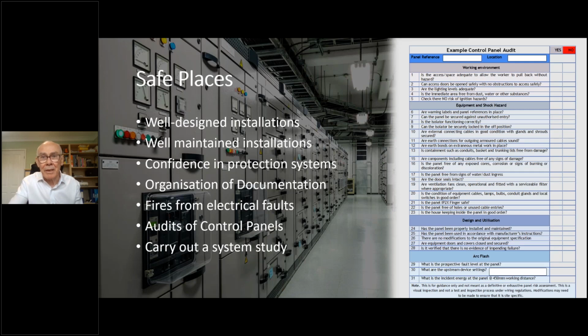That form in itself, from my own experience, would allow people to have a formal look within their control panels, which is the brains of the operation. If you talk about switch gear, control panels, transformers, generators, these are the heart of a production facility, but the brains is the control panels, the things that control the equipment itself. These are expensive things to replace if they go wrong, and having audits allows us to find issues before they become incidents, then carrying out system studies to know what the fault levels are, and perhaps arc flash levels throughout the network as well.